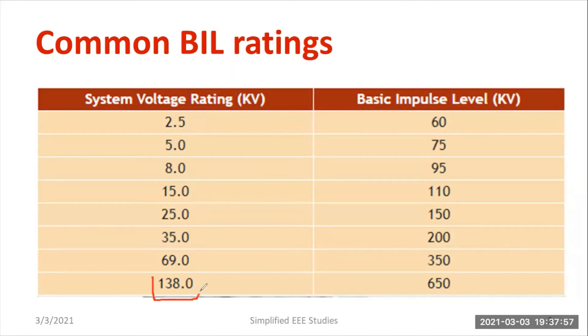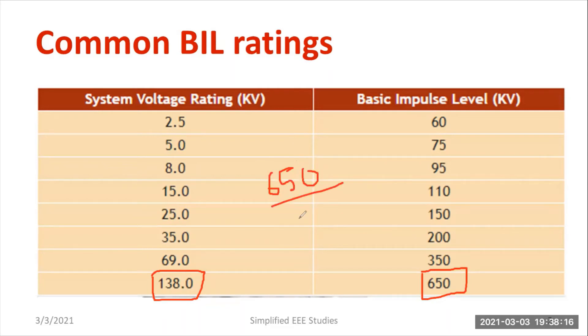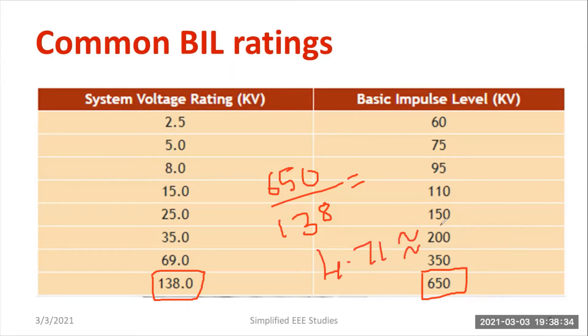Let us consider the last example. Suppose for your switchgear — you are operating a switchgear with an operating voltage of 138 kV — the Basic Impulse Level recommended is 650 kV. So 650 divided by 138 equals 4.71, approximately equal to 5. That means you are providing 5 times the operating voltage as insulation strength, so the dielectric breakdown strength is maintained at 650 kV.